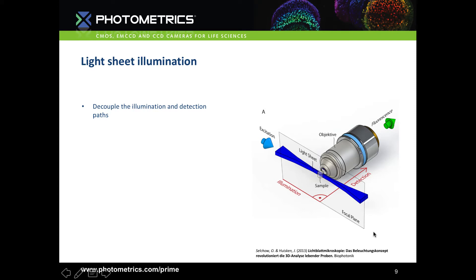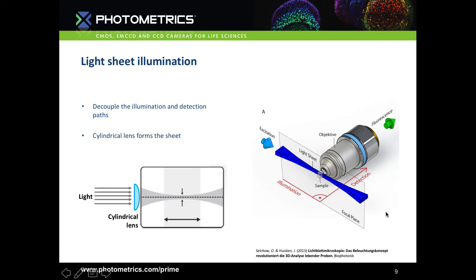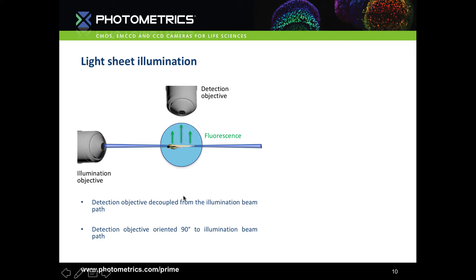We achieve this by decoupling the illumination and detection paths. The excitation beam comes in through an objective on the side, generating the lightsheet. At a 90 degree angle to the illumination is where we have our detection objective. We form the sheet using a cylindrical lens in the light path, which causes the beam to converge in the middle and diverge out again — this is the beam waist — forming a sheet of light through the sample, with fluorescence detected through the detection objective above.